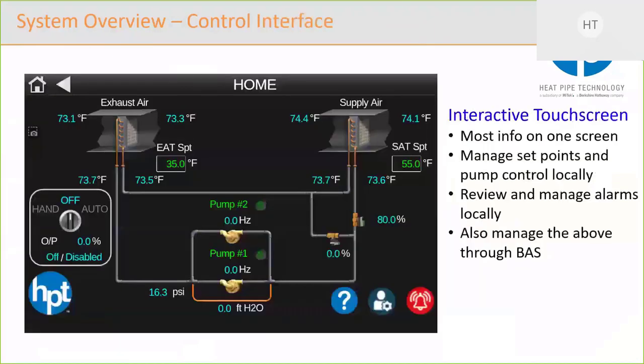So this is a snapshot from the screen. As I said, we're trying to get most of the information on one screen. You can manage the set points from this screen. So you can see on the right here that the supply air set point, SAT, is a default of 55. That's typically what people try to heat to. And on the left, we have an exhaust air set point, 35. So the items in green are items that you can click on and edit straight on the display or through the BMS. You can also review and manage alarms.